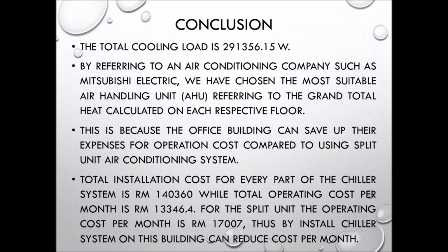Finally, as a conclusion, we have calculated the total cooling load based on the cooling load on each respective floor. The total cooling load is 291,356.15 watt. By referring to an air conditioning company such as Mitsubishi Electric, we have chosen the most suitable air handling unit, which is the AHU, referring to the grand total heat calculated on each respective floor. The centralized air conditioning system has been chosen for installation.